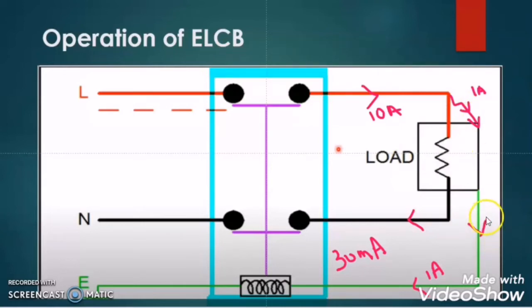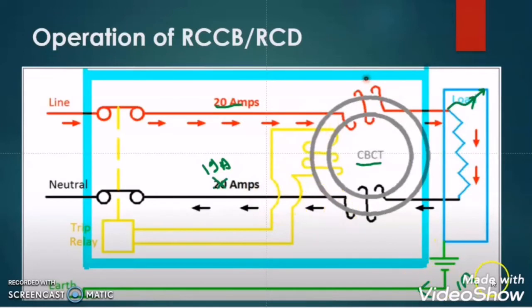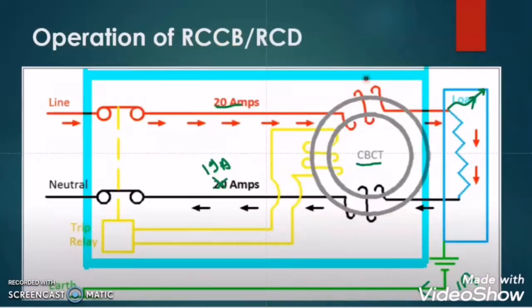Suppose there is a leakage but due to some issue the earth conductor is not connected with the load. Then the tripping coil of the ELCB will not energize because the earth is missing. So even though there is a fault current, the ELCB will not trip if the earth is missing. In the RCCB case, there is no role of the earth conductor in order to trip the RCCB.